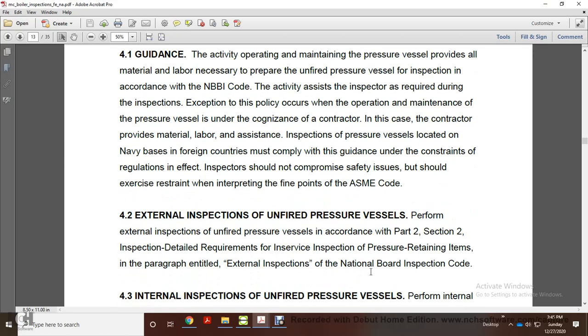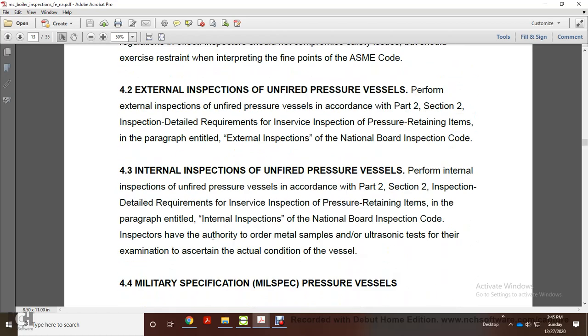4.2 External inspection on unfired pressure vessels. Perform the external inspection on unfired pressure vessels in accordance with Part 2, Section 2, inspection detailed requirements for the in-service inspection pressure-retaining item of the paragraph entitled the External Inspection National Board Inspection Code. 4.3 Internal inspection on unfired pressure vessels. Perform internal inspection on unfired pressure vessels according to Part 2, Section 2, inspection detailed requirement for in-service inspection pressure-retaining items in the paragraph entitled the Internal Inspection National Board Inspection Code.